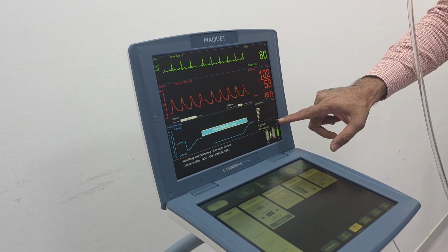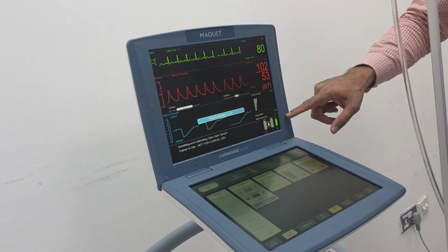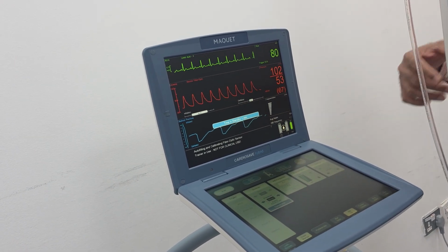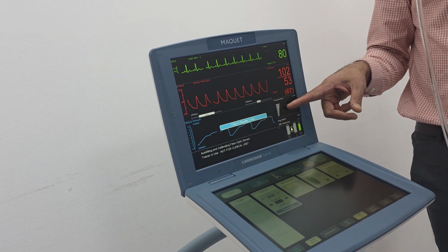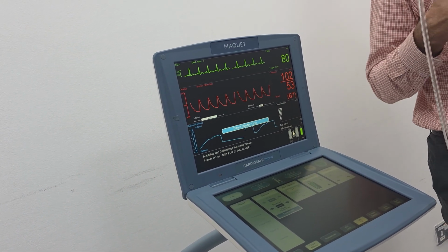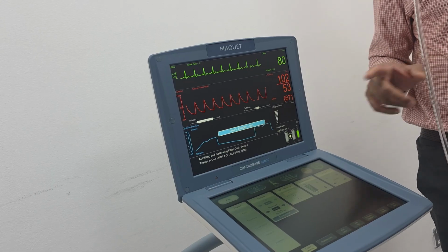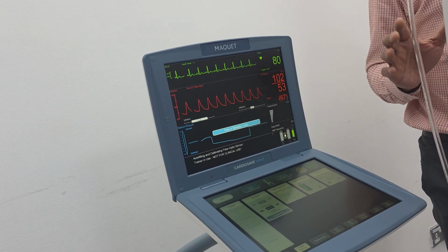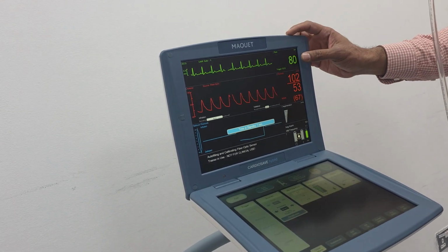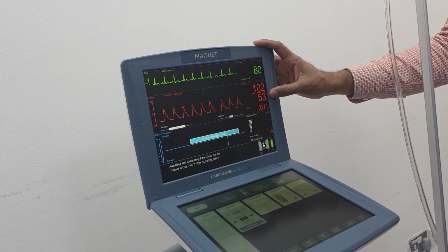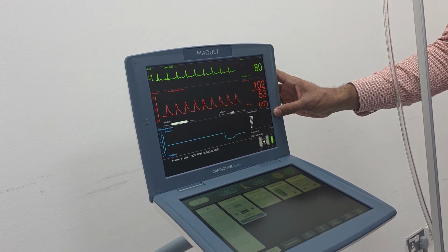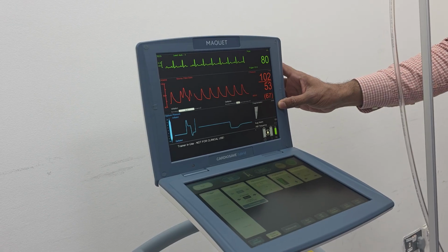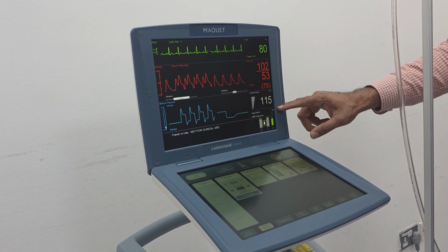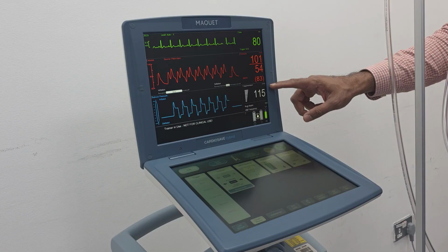Battery is charged fully. Augmentation is set automatically. But if you wish to set it, because you know this augmentation alarm, we cannot guarantee for that. It's totally based on the patient clinical conditions, right? It will come, and the balloon inflation timings. But we have the values. So ECG is here, systolic, diastolic, mean. Okay. Now we have the augmentation. So this one approximately less than 10 mmHg it will set.